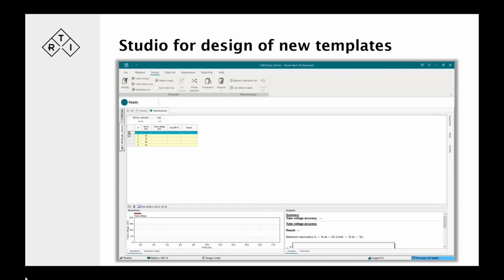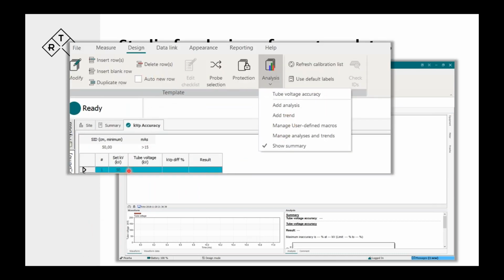So to get these kinds of templates in shape, we've got a studio where we can provide design of the different templates. We can add rows and columns. We can add analyses that will then give us pass-fail criteria during the test that we're performing. The criteria are set up and selectable, typical for X-ray testing. So it's for accuracy, for linearity, for reproducibility, etc. Those are all preset tests that can be selected. And of course, insert rows and modify the graphics and the look of it to get it to work according to the tests that you as a customer would need to perform.